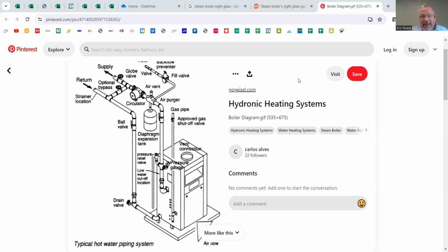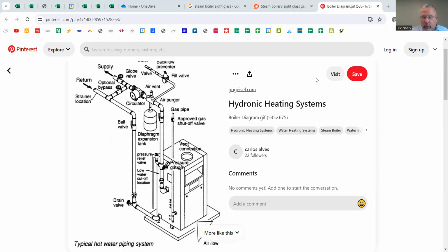Essentially, what that does is it takes your incoming water pressure, which is usually around 20 to 30 PSI, and reduces it down to what the boiler wants. I believe it's 12 PSI. So when the boiler is cool, when the water is cool, it shrinks. It takes up less space. That heating and cooling, expanding and contracting. If any water needs to be added, the fill valve is going to bring that boiler back up to 12 PSI. When the boiler fires and starts running, it's going to run up to around 18, 20, or maybe 25 PSI. At that point, it's not going to add any water until it cools back down.